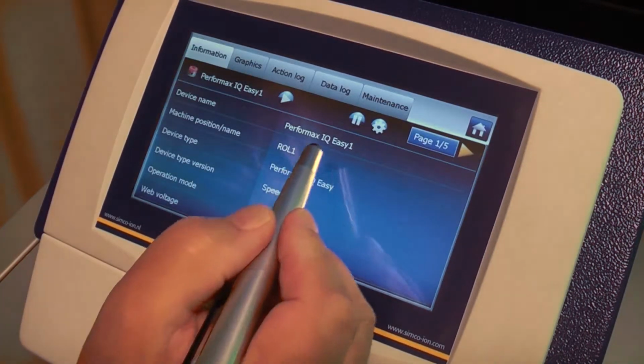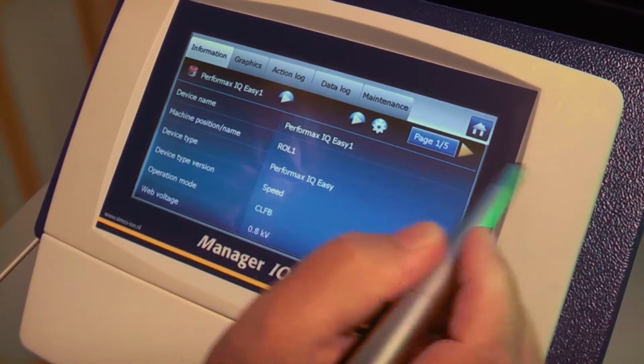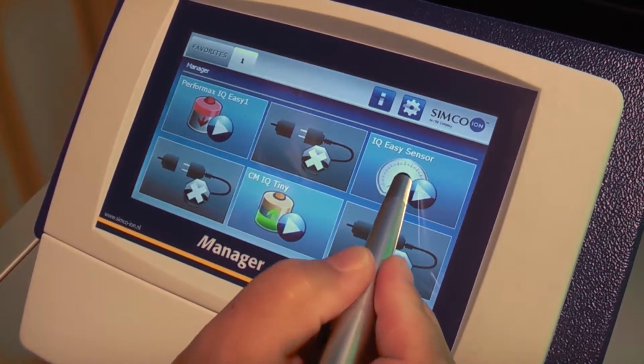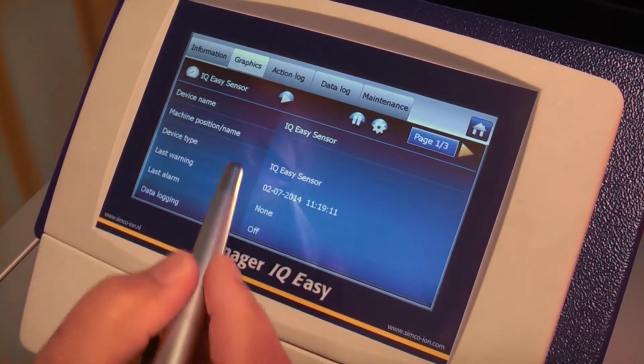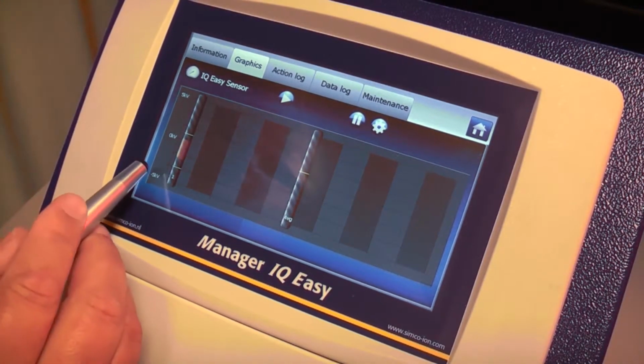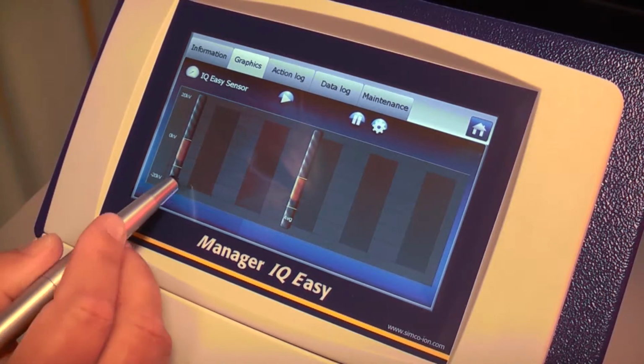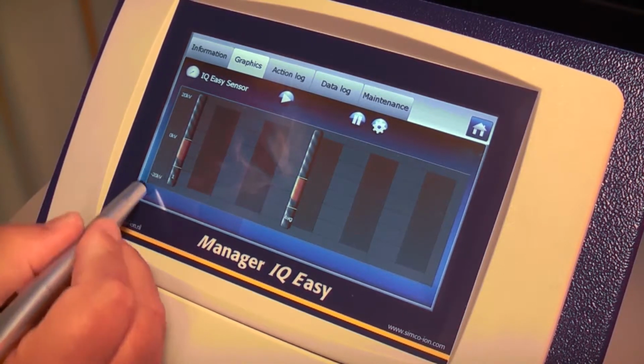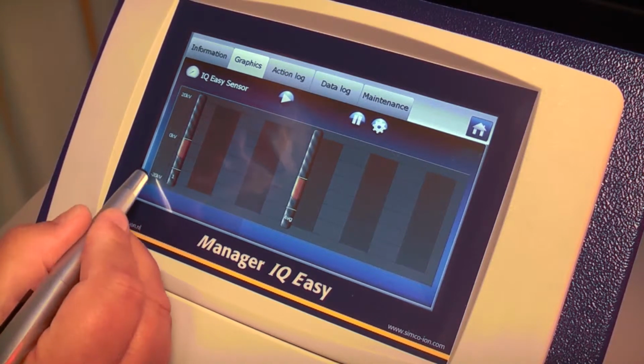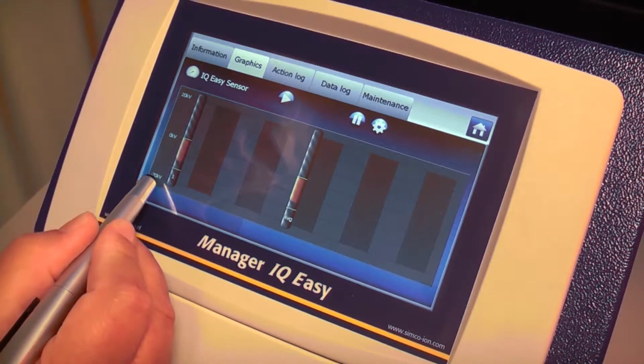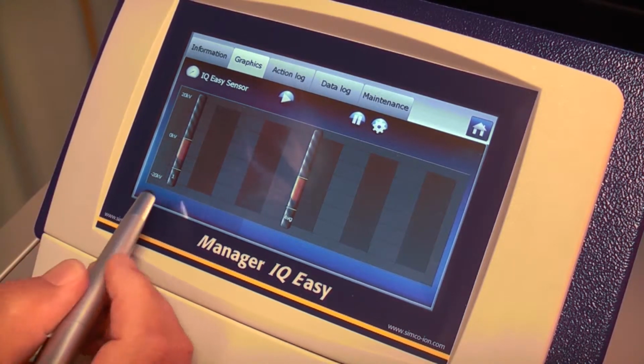When I switch off the antistatic bar again and go back to the sensor, I can also see here what is happening. The scale has now changed from minus 5 kilovolts to minus 20 kilovolts.